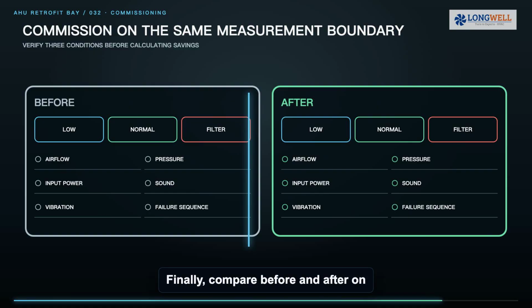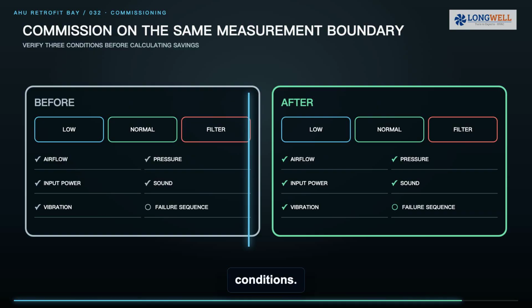Finally, compare before and after on the same measurement boundary. Verify airflow, pressure, electrical input, sound and vibration at normal, low load and worst resistance conditions. Prove the control and failure sequence. Only then calculate project savings from measured power and real operating hours.